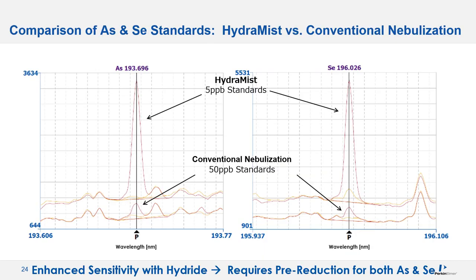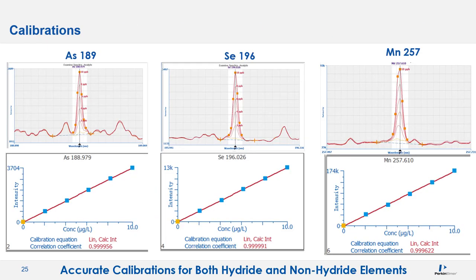Looking at initial HydraMist results: conventional nebulization of 50 ppb standards showed relatively low signals, but with the HydraMist at 5 ppb we saw much higher sensitivity, demonstrating the enhancement from hydride introduction. Calibration curves for arsenic and selenium by hydride and manganese by conventional nebulization were run at 2, 4, 6, 8, and 10 ppb — the 2 ppb standard was clearly visible for both arsenic and selenium, as well as manganese. Curves were very linear, showing enhanced sensitivity for hydride elements while simultaneously achieving good sensitivity for conventional analytes.